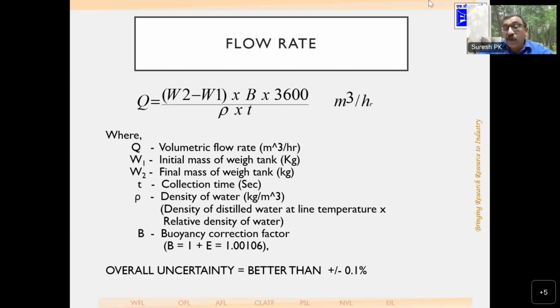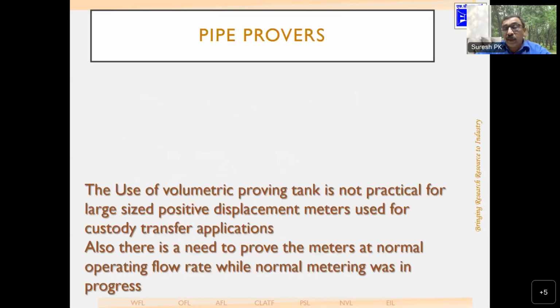First, you have to find out the general behavior of the flow meter before you correct it. Whether it is linear, whether it is scattered, or whether it has a slope. If it has a slope, what is the slope? And if you adjust the flow meter at a particular flow rate, what will happen to the accuracy at other flow rates? All these things have to be considered before you make the final correction on the flow meter. After you correct the flow meter, you need to verify its accuracy once again, to ensure that it is repeating and that no error has occurred during the correction or the calculation. So overall uncertainty is better than 0.1% in the flow rate in these gravimetric systems.